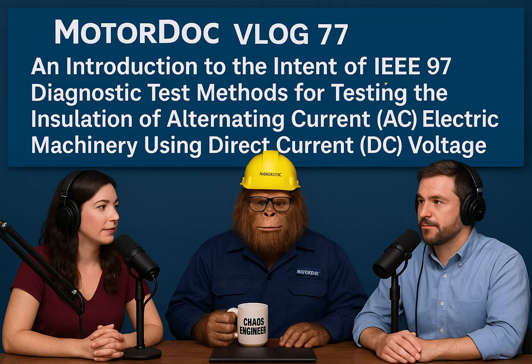What about surge capacitors? Those are often right there at the machine terminals. Surge caps are a major influence on IRPs. They cause a very, very fast initial rise in the IR, followed by a really sharp knee, a sudden change in slope, and then the IR level will tend to plateau out at or near the resistance value of the capacitor's internal bleed resistor. So it doesn't look like insulation behavior at all. Not really. This behavior completely swamps the machine's true insulation response.